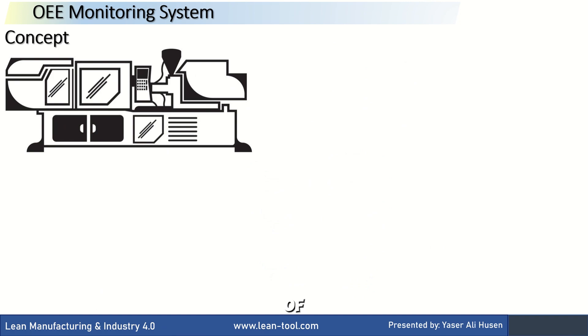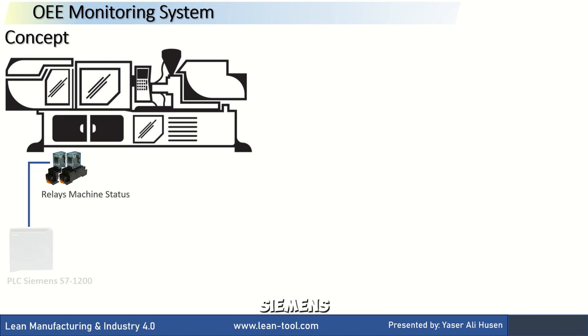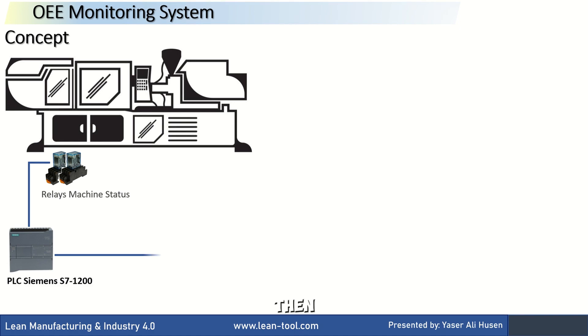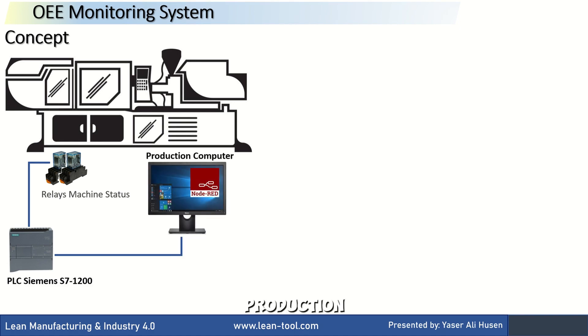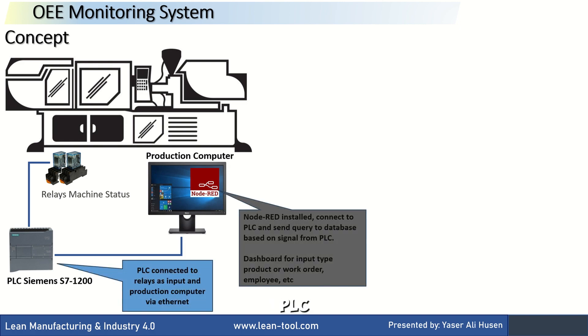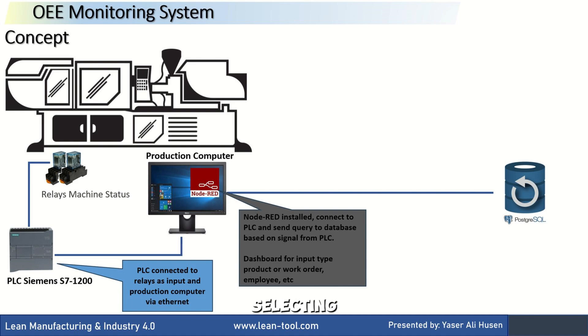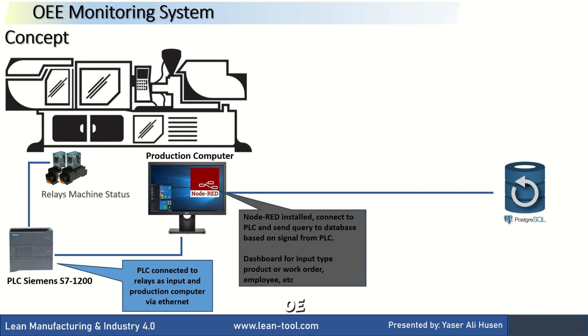In the concept of collecting OEE values from machines, I am still using the approach I showed in some of the previous videos. Each machine has some relays that connect to a Siemens S7-1200 PLC. The PLC then connects to a production computer, which functions as the back-end, reading values from the PLC and sending queries to the database. The production computer also serves as the front-end with a dashboard for additional inputs like selecting work orders, entering employee details, and monitoring the machine's OEE values.